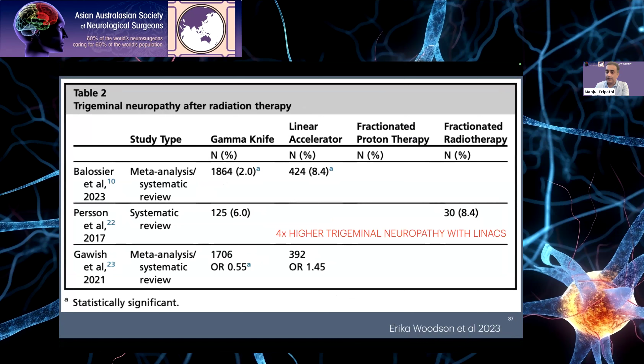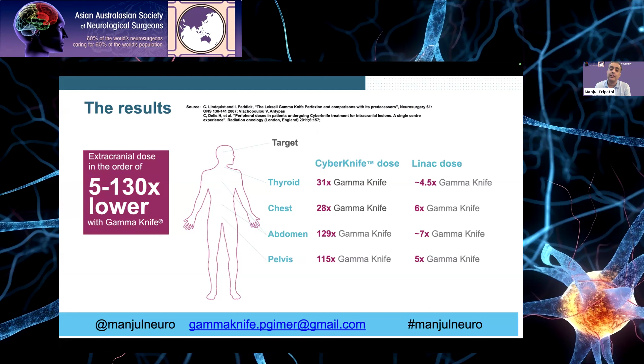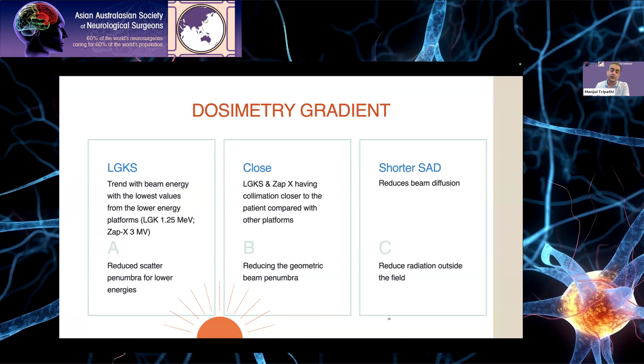Apart from it, while we are treating these tumors, we need to look that we do not pave a way for the creation of new tumors over the long course of time. With its sharp dose fall-off, the chances of extracranial radiation exposure are 5 to 130 times lower with gamma knife in comparison to CyberKnife and LINAC-based technologies. That is because of the sharp dose fall-off and the low energy source of the gamma knife and the ZAP-X machine. They reduce the scatter and decrease the chances of radiation exposure because of the shorter distance between the source and the target.